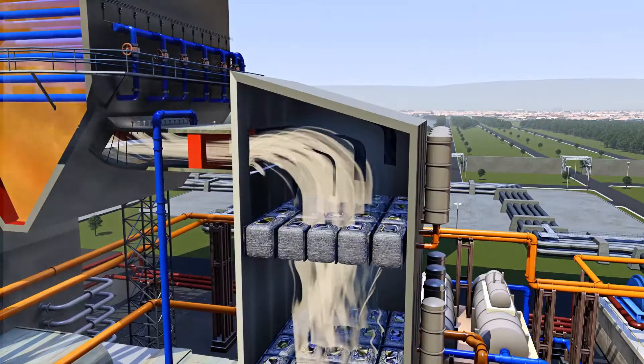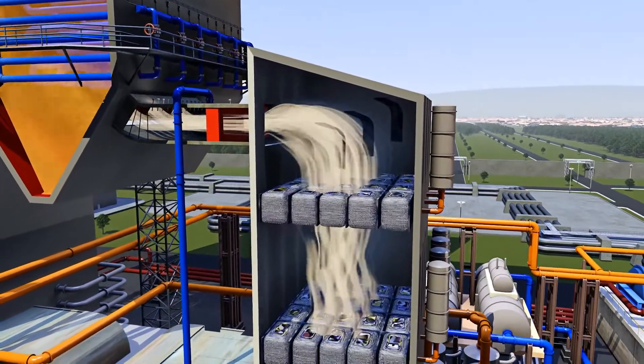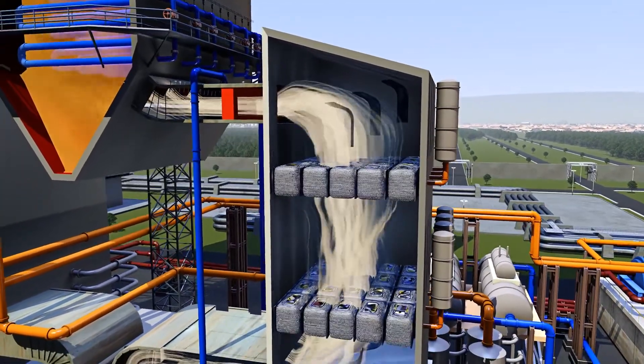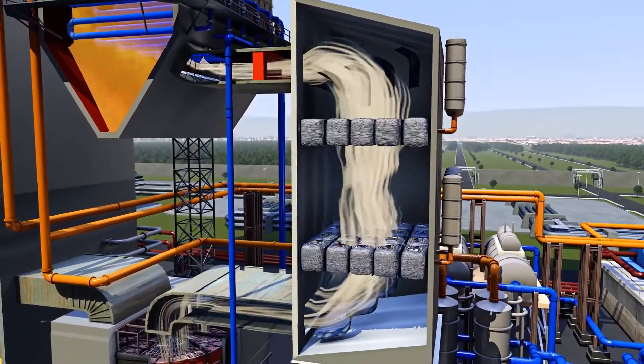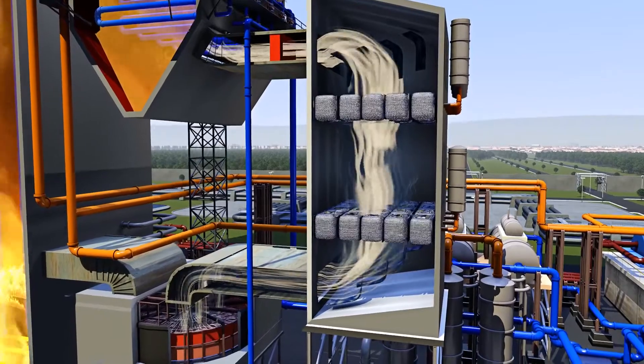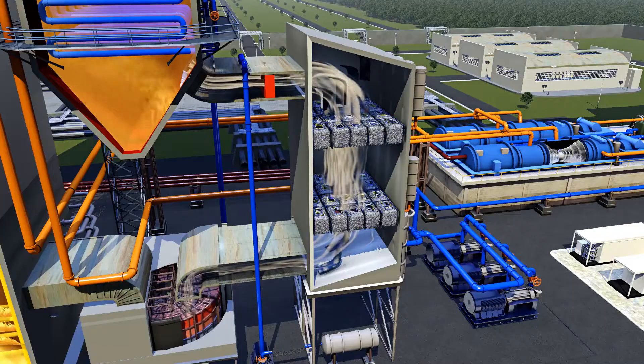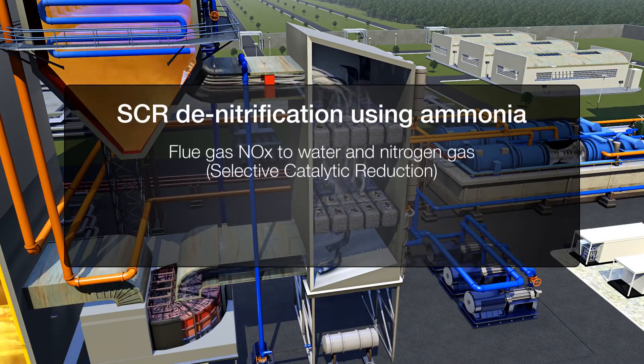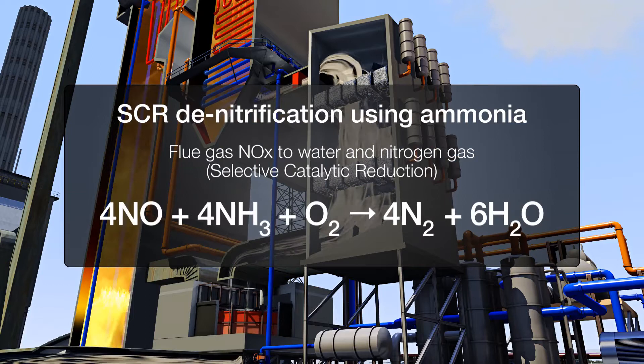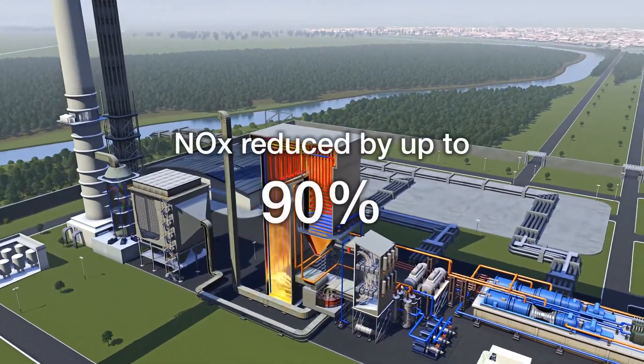The role of the flue gas denitrification plant is to remove residual nitrogen oxides in the flue gas. These plants fall into two main types. Selective catalytic reduction, or SCR, plants add ammonia to the flue gas before passing it through a multi-bed selective catalytic reduction process. As the NOx passes through, it is converted into water and nitrogen. These plants are highly efficient, achieving a removal rate of around 90%.